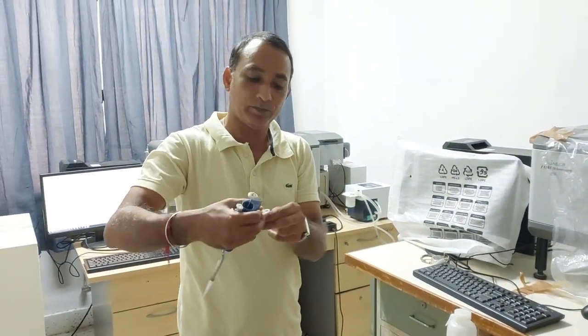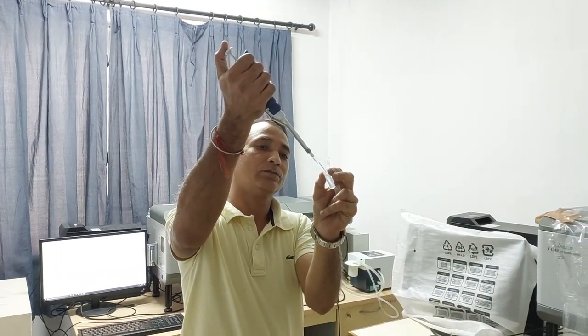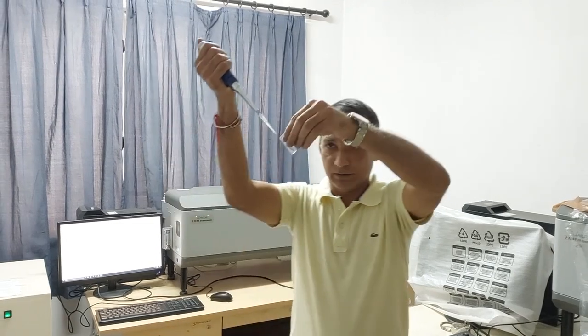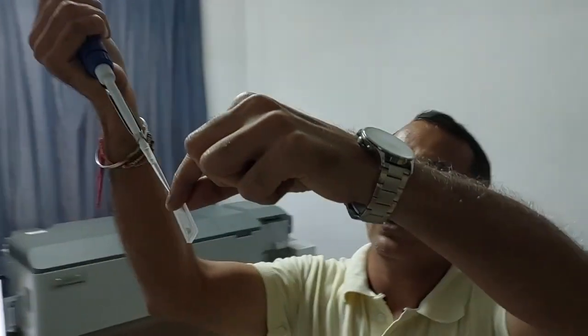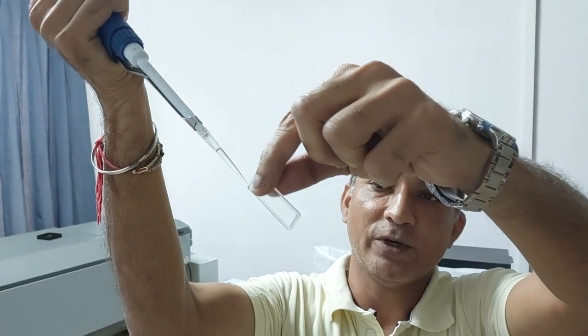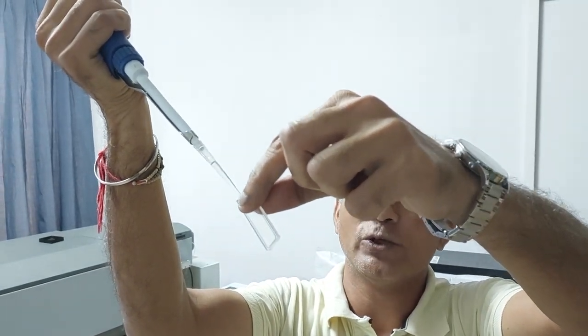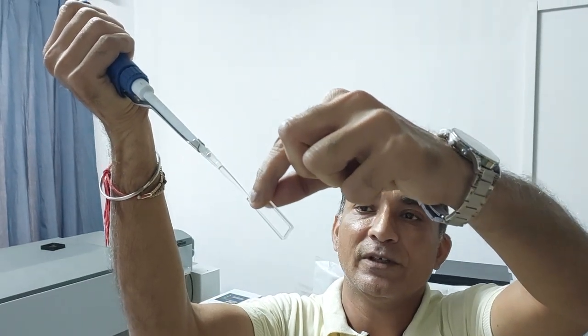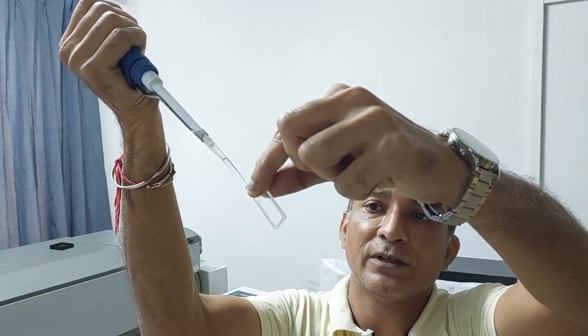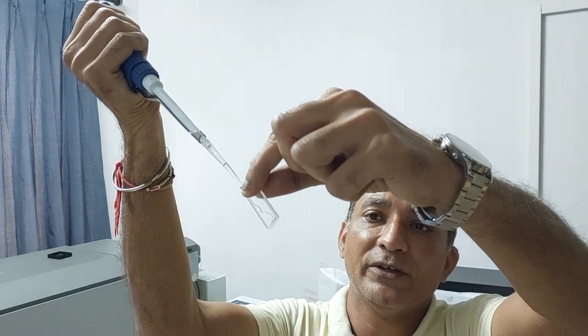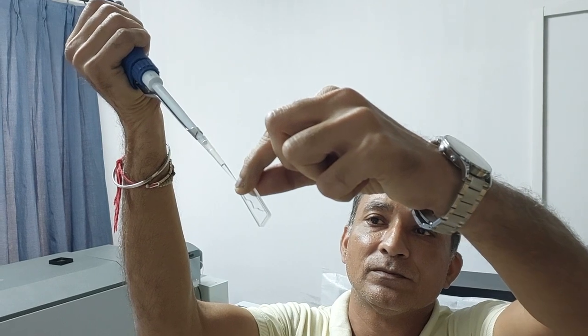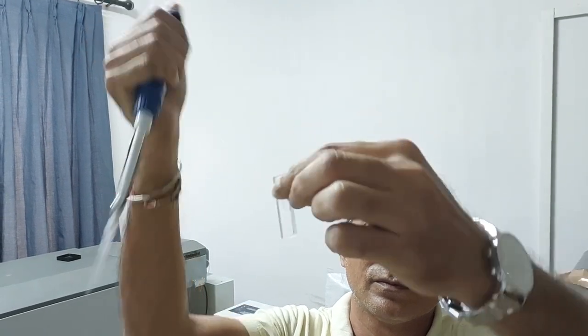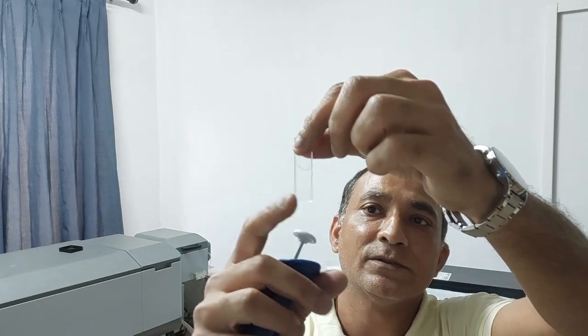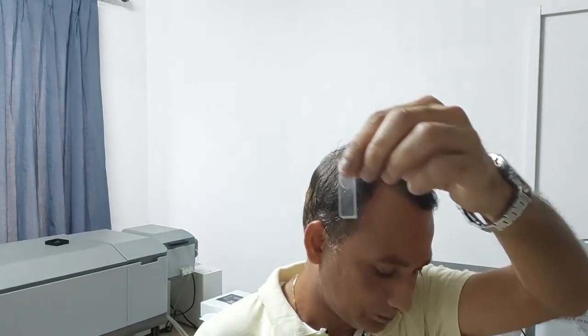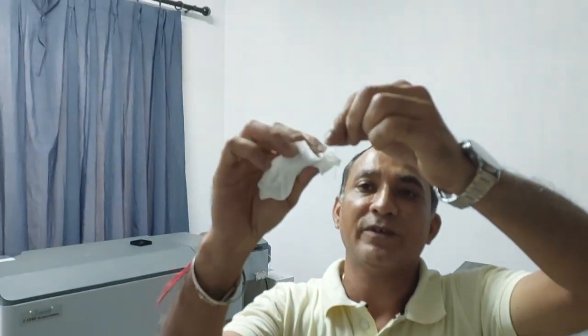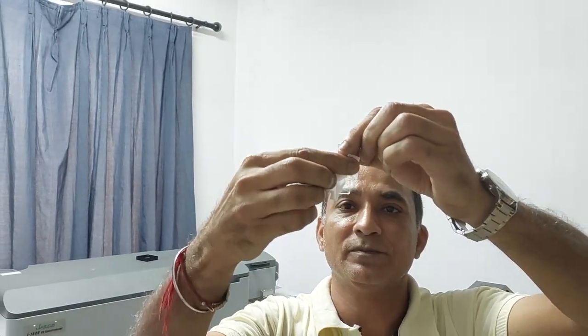This will be our blank. You add the blank or whatever sample you are adding to the edge of the cuvette, ensuring that no bubbles enter inside the cuvette. So you can gently push down the solvent, ensuring that no bubble enters the cuvette. You can gently tap the cuvette to get a nice meniscus at the top. You can then wipe the surfaces using lint-free tissue paper.